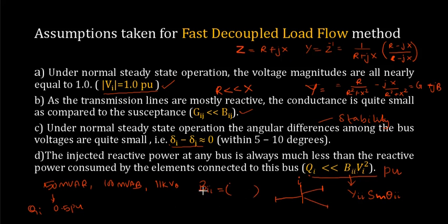BII. So this BII obviously will be a large value, because your admittance, the reactance value will be in the range of 0.5 or something. So if your reactance value is 0.5 or in that range, obviously the inverse will be a large value. So once you take the inverse, this BII will be in the range of say 50 to 60 in ohmic value, and once you convert that into the per unit value using this base 100 MVA 11 kV, I'm taking an example.